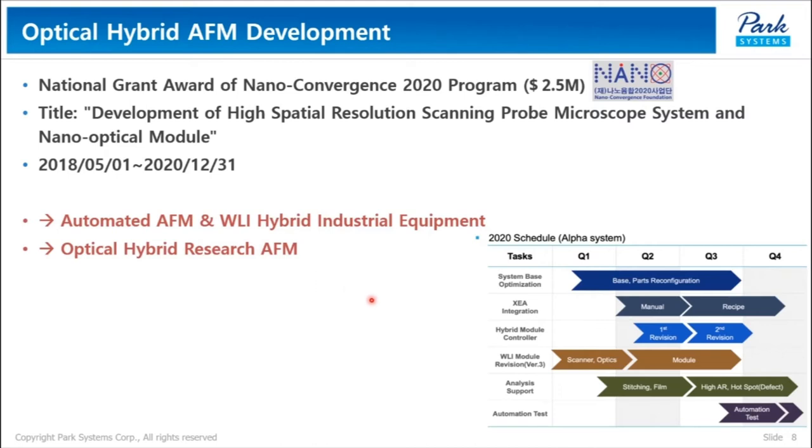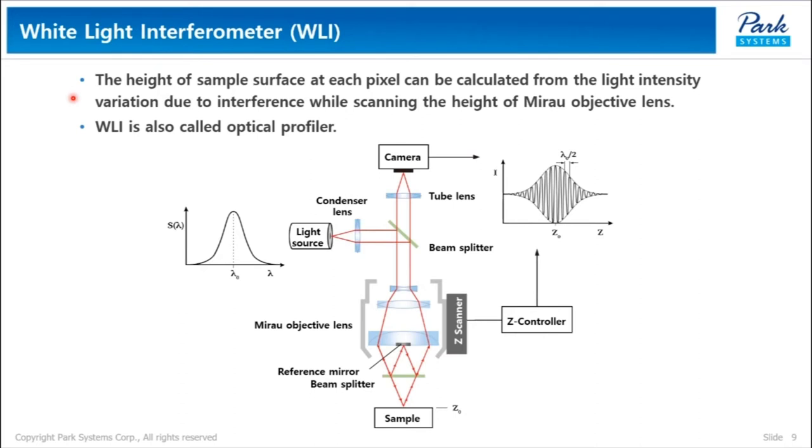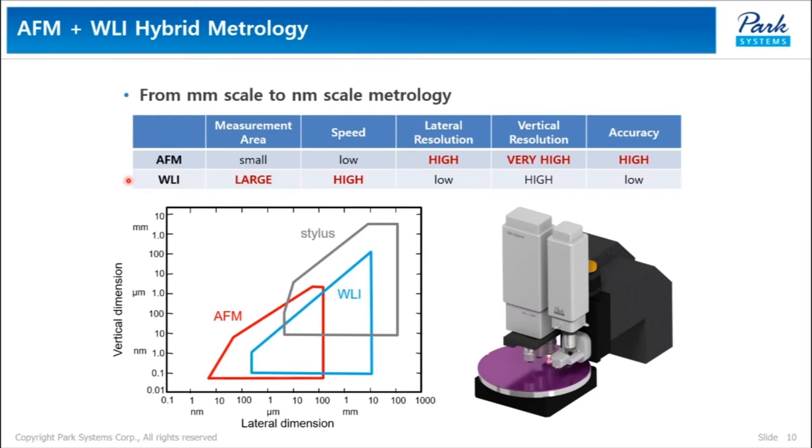We are finishing the AFM-WLI hybrid alpha equipment this December and starting a joint evaluation program with one of the major semiconductor companies. In WLI, the height of the sample surface at each pixel can be calculated from the light intensity variation due to interference while scanning the height of a Mirau objective lens. Since WLI can generate 3D images with height information, it is also called an optical profiler. AFM technology has a measurement area of up to 100 micrometers and is suitable for high-resolution and high-accuracy imaging, but not suitable for full-die range measurement. WLI technology is suitable for measuring full-die areas of hundreds of micrometers to a few millimeters, but produces lower resolution and accuracy compared to AFM.